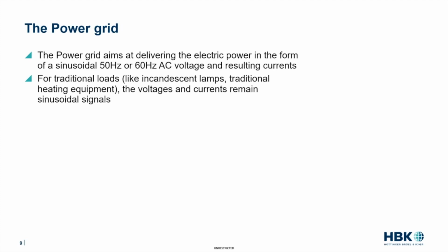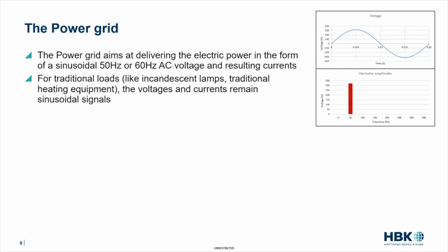And a few decades ago, when the loads, or the devices connected to the power grid, were still very simple, like incandescent lamps, traditional heating equipment, but also certain types of electric motors, all the voltages and currents in the power grid remained sinusoidal signals, because basically all those loads were very decent, very resistive and very linear. So if you started out at a power plant with a sinusoidal voltage, then you kept sinusoidal voltages and sinusoidal currents. So what you would see, if you looked at a voltage or a current, would be a very nice sine wave, as you can see in the top picture here.